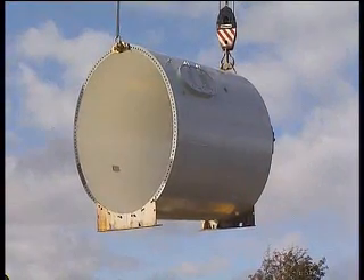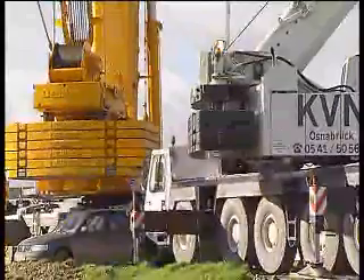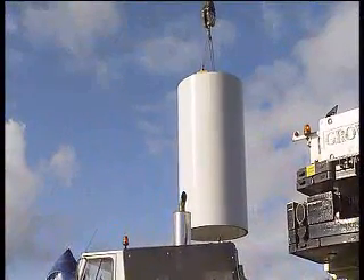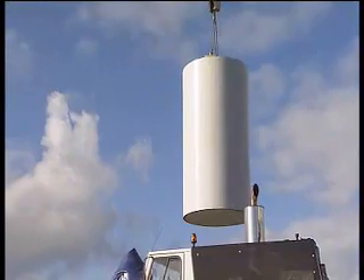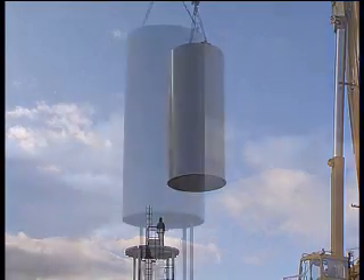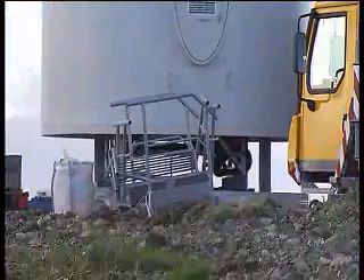The second vehicle is the base tower section. This is erected between two cranes — a 500 tonne telescopic crane and a 100 tonne tailing crane. These components are lifted by the two cranes off the vehicle and we top and tail until the tower section is in a vertical position, where the tailing crane is disconnected and the main crane lifts the base tower section and places it over the top of the PPM, and our guys then bolt it to the foundation adapter piece. The same system is carried out for the second and third tower sections.